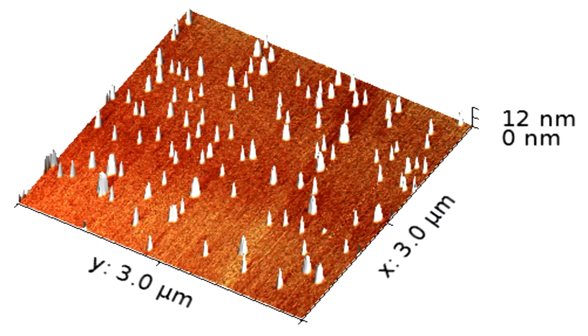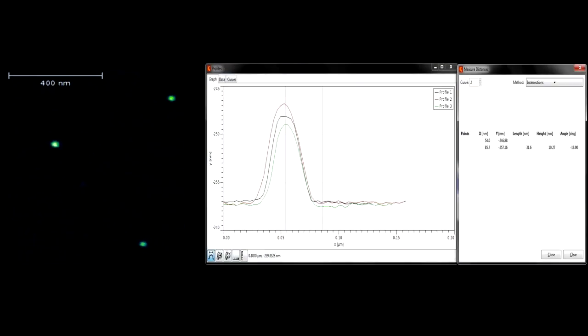Utilizing the TT2 is an affordable way to categorize nanoparticles less than 50 nanometers in diameter. An important capability is being able to measure particle size distributions.